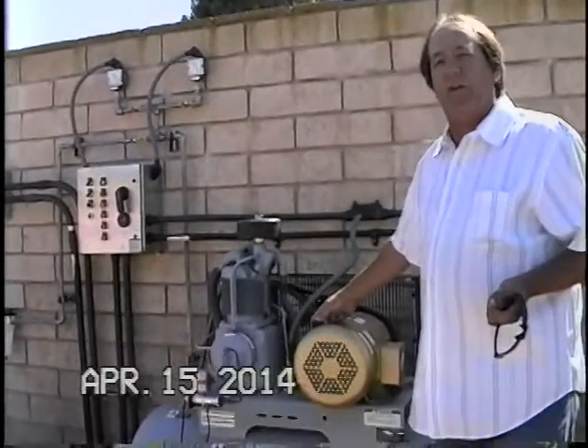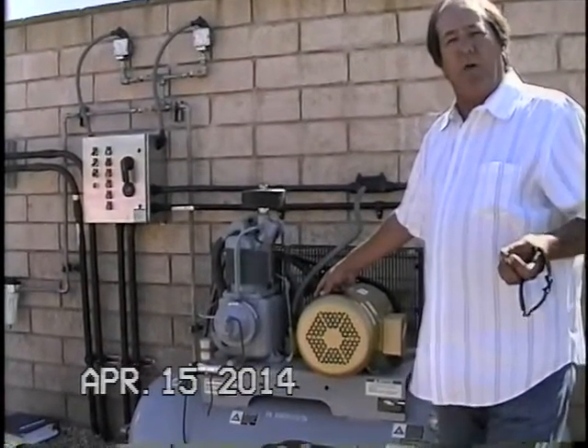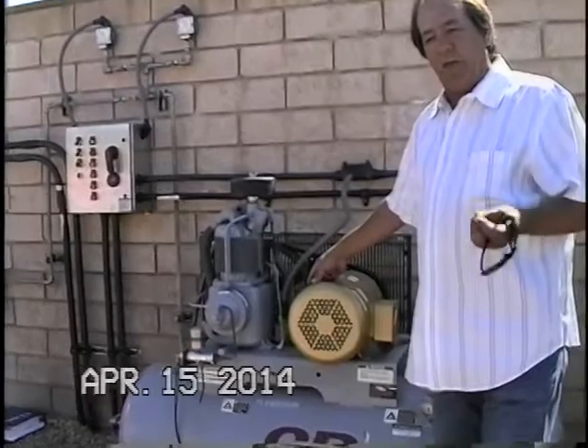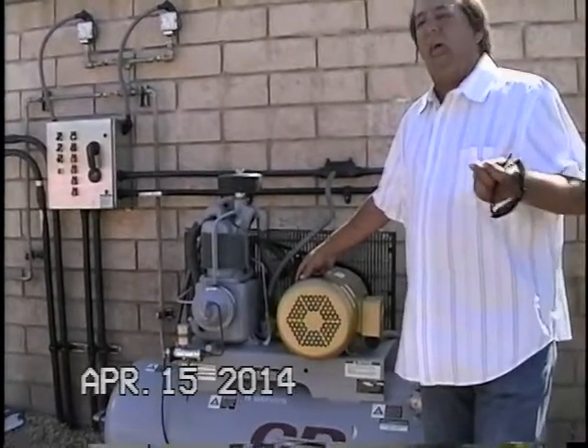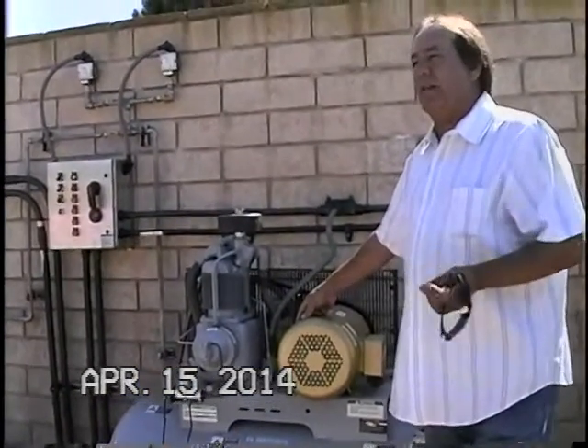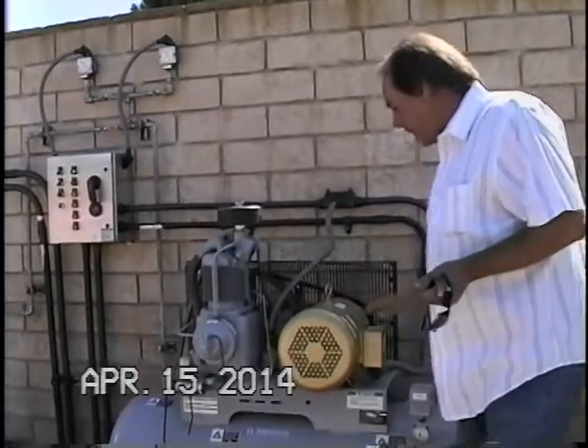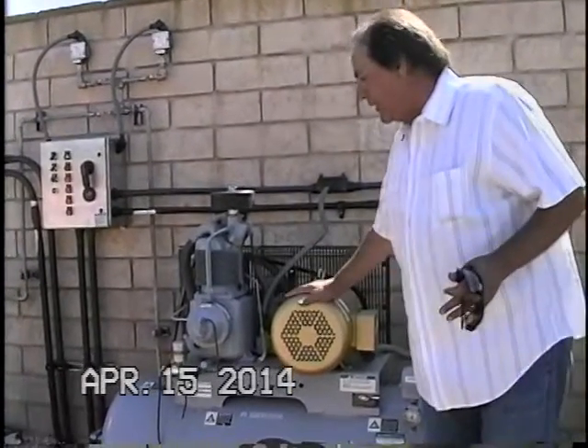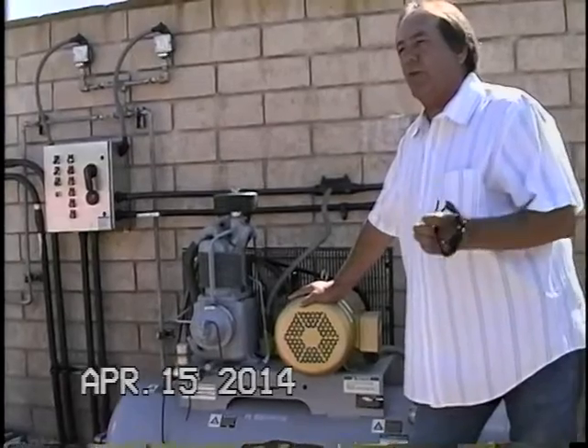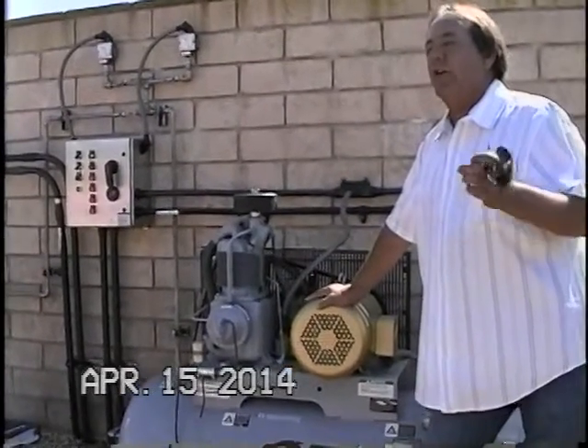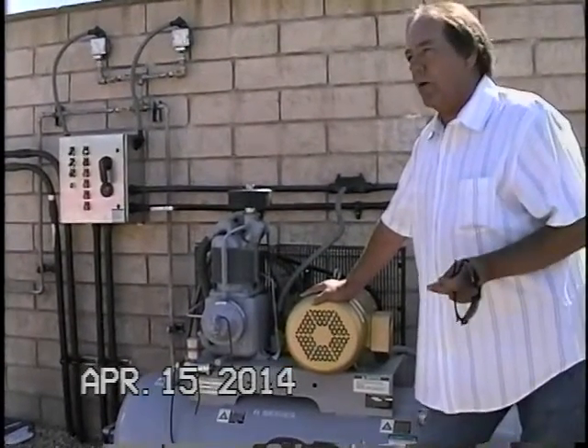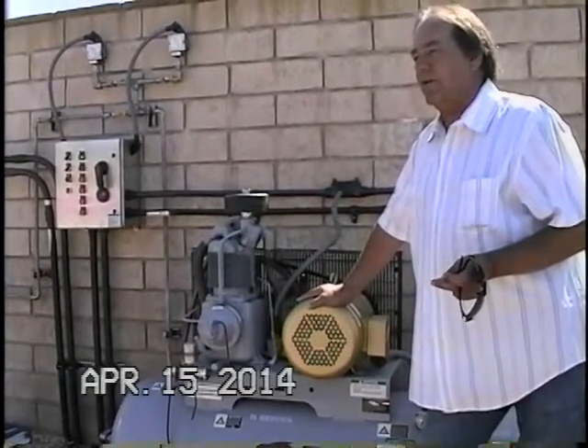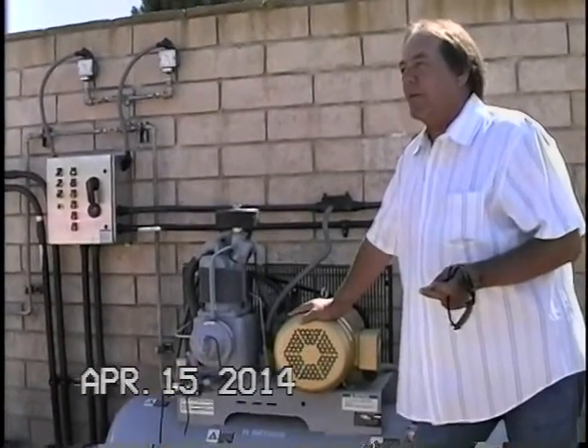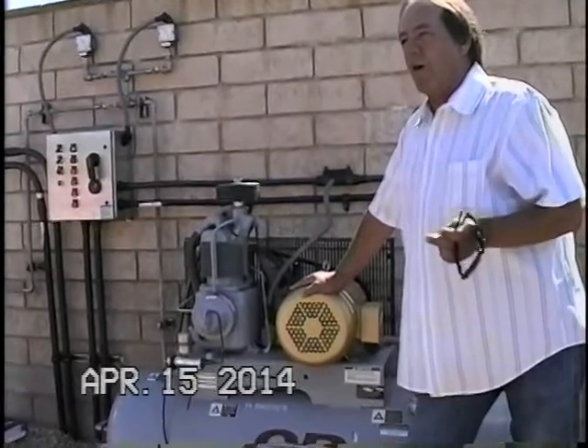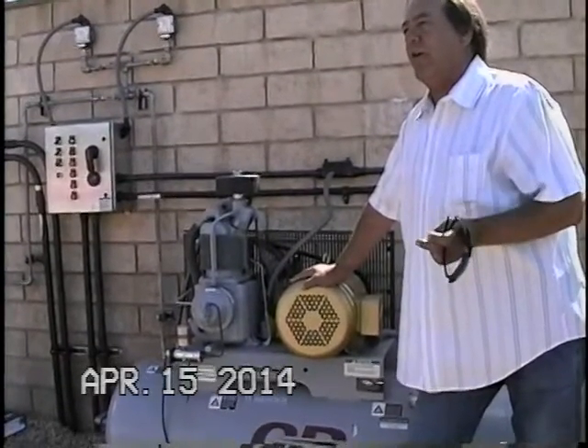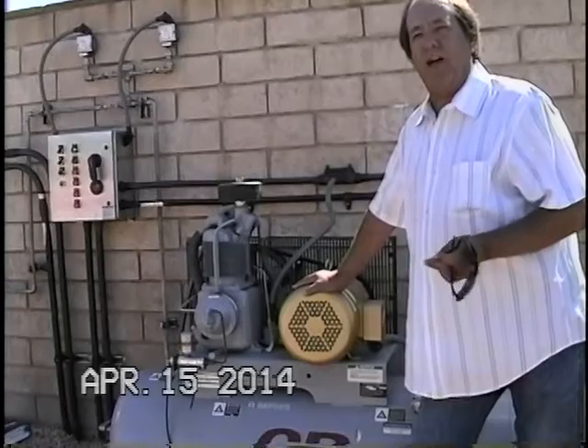Your oil change intervals are inside your O&M manual. You need to double check those and change those as required, as stated, because I believe that you've got a fairly good warranty on these, but you need to make sure that you do the oil changes and you use Gardner Denver oil. There are other compressor oils out there, but if you want to maintain your warranty on these, it's very important that you use their specified oil.